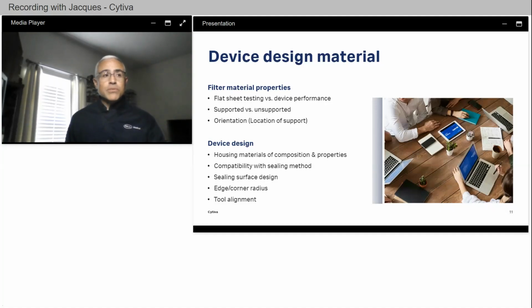Are they similar materials? How different are the thermoplastic properties of these components going into the device? Is the sealing method I'm considering compatible with both the housing material and the filter membrane? Is the design of the sealing surface adequate to ensure a strong seal without damaging the membrane or creating excess flash? And how will the filter material be held in the device during the sealing process? Careful consideration of these different aspects will help avoid pitfalls further on in the development process, as well as once it is in the production stage.